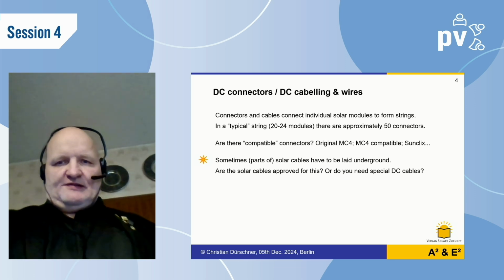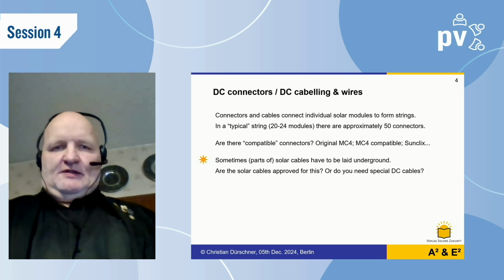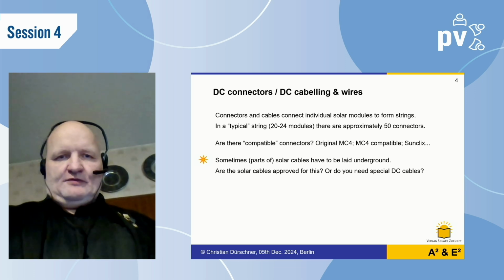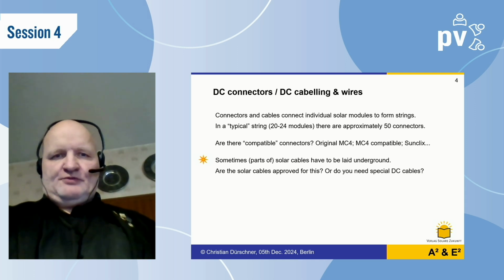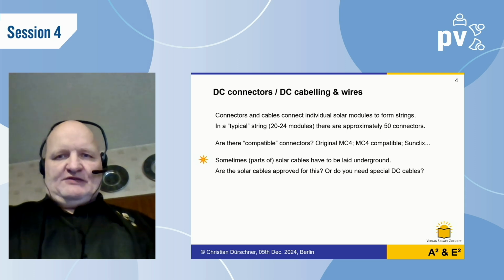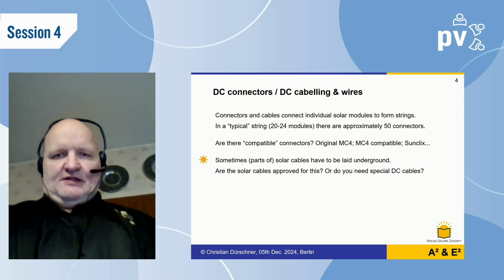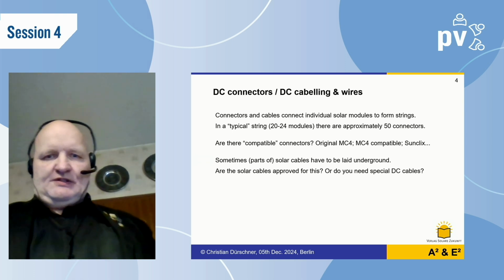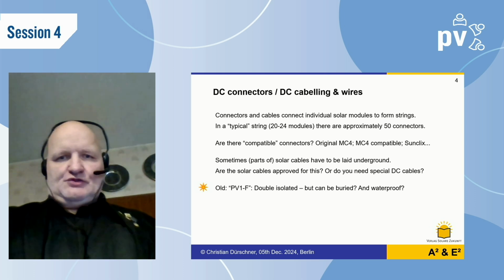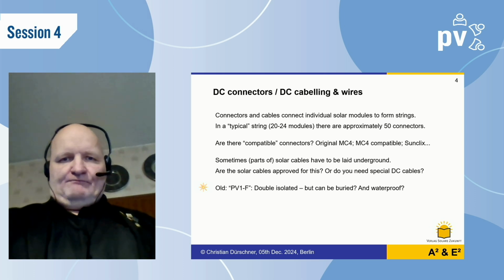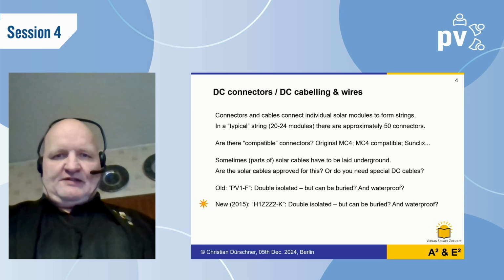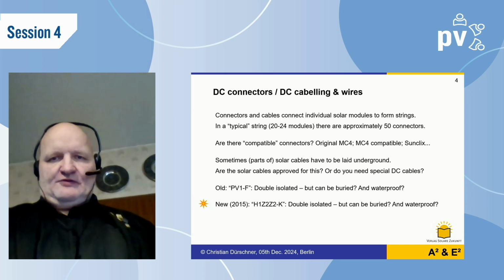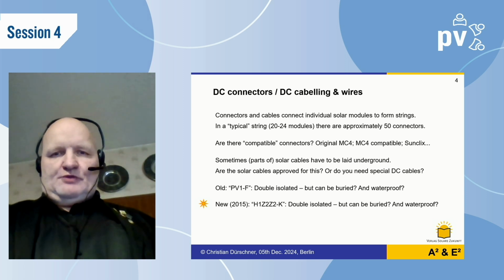The second thing is that our DC cabling is made for using on roofs, but in ground field installations you sometimes have to put it into the ground. The question is: is this tested for that? Is it specified for that? I can tell you that the original specification from the TÜV, also the technical standard from 2015, does not look at waterproofness, does not look at whether the cable can be buried in the ground.